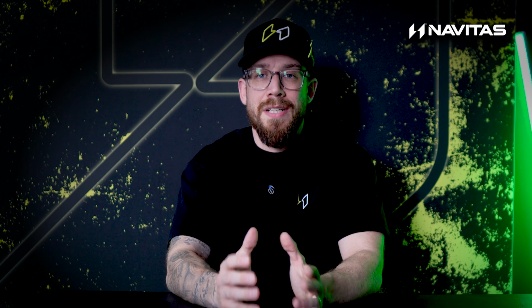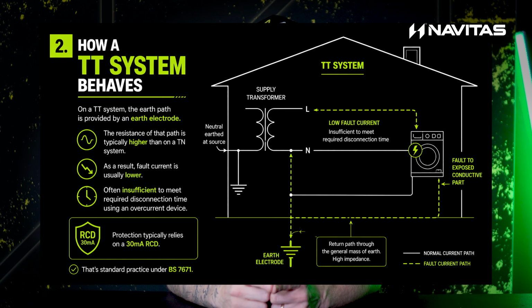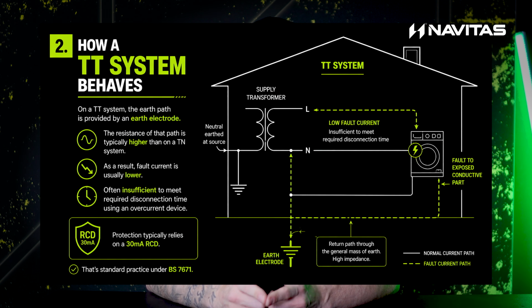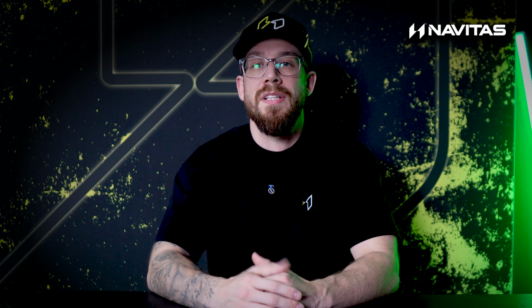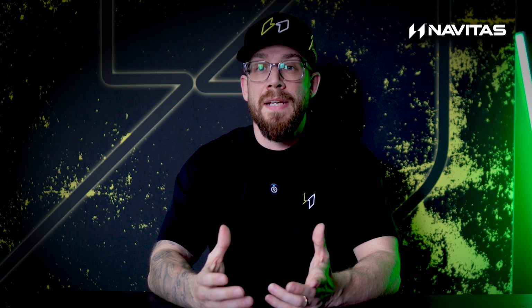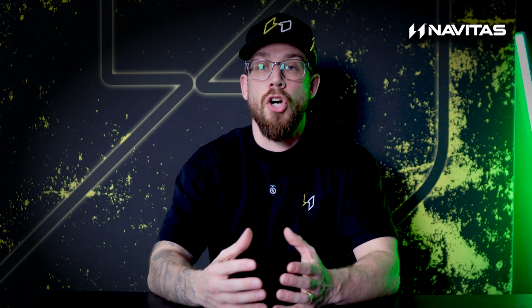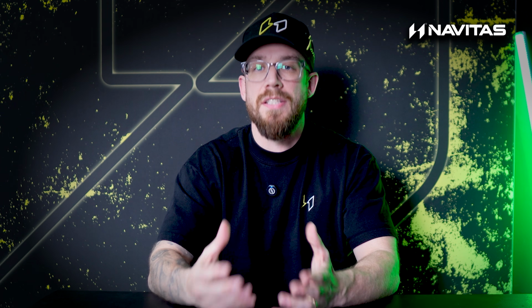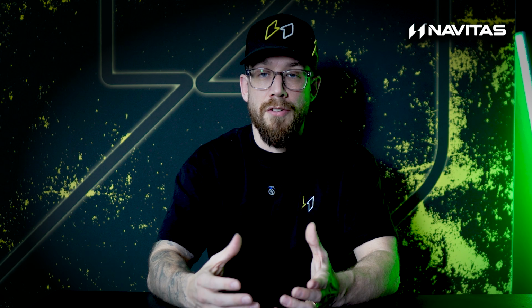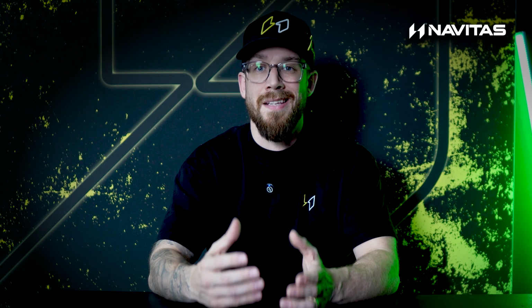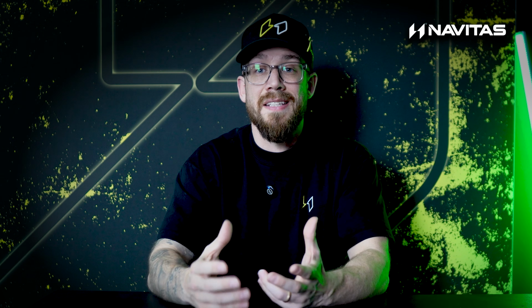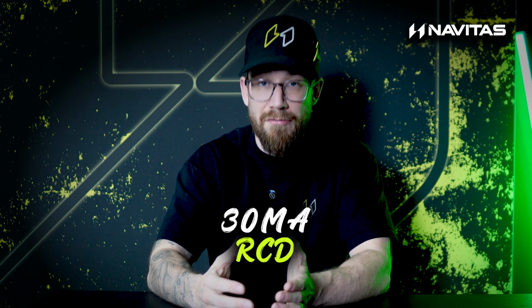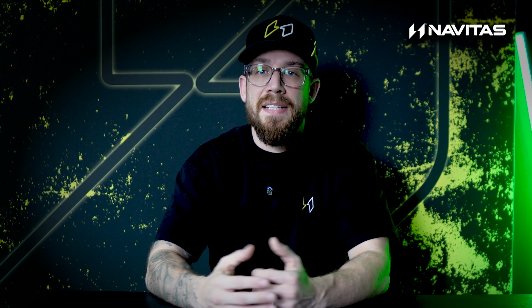of device. On a TT system, the earth path is created by an earth electrode. That means that the resistance of that path is often higher than you'd find on a TN system, for example. Because of that, when a fault occurs, the fault current is usually lower. So in many cases, it's not actually high enough to operate an overcurrent device in the disconnection time required. So instead, the disconnection relies on the 30 milliamp RCD rating. And that is standard practice under BS 7671.